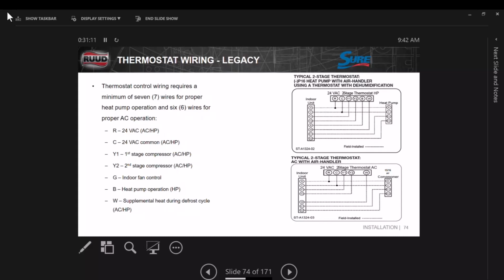It's a lot less wires you have to deal with outside. On the air conditioners, the same thing. All of our wires are going to go from the thermostat to the air handler on a typical thermostat, and then our E1 and E2 and RC comes to the outdoor unit. Now this is on everything except for the 15 SEER heat pump. What's good about those is you can't hook them up wrong. If you do, it won't work. That's right. If you get them backwards, it's just not going to communicate.